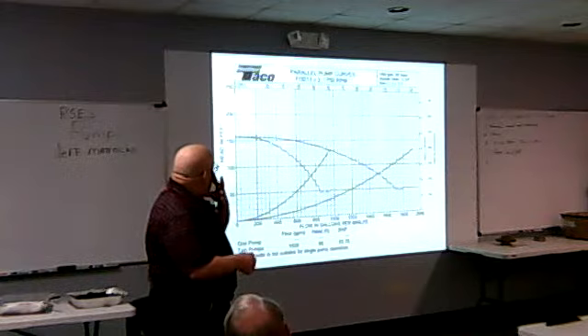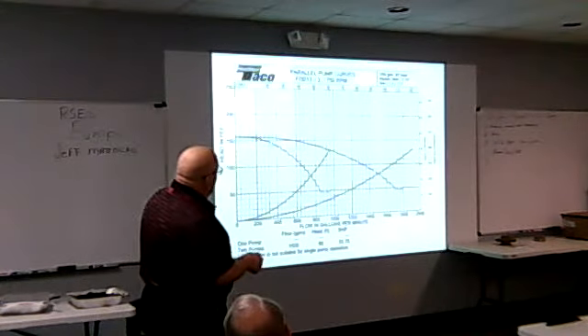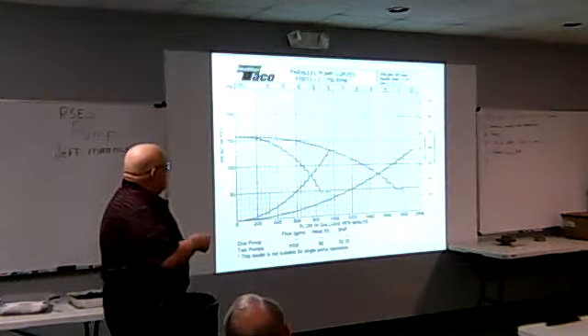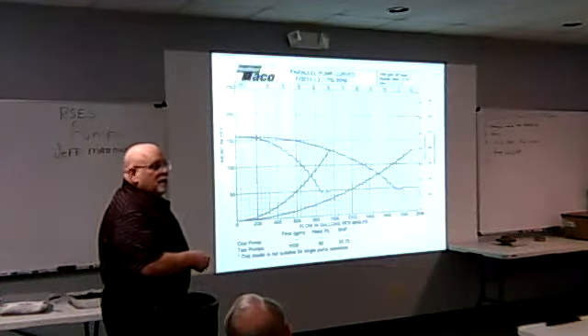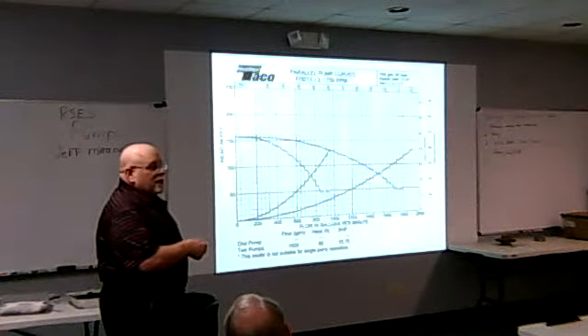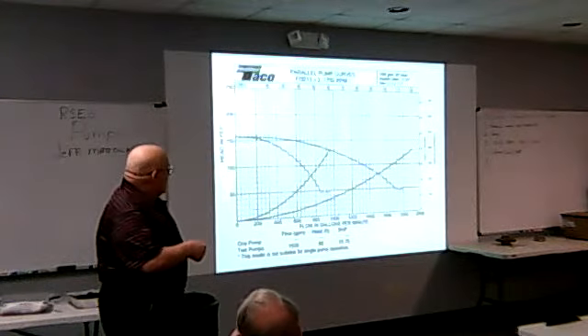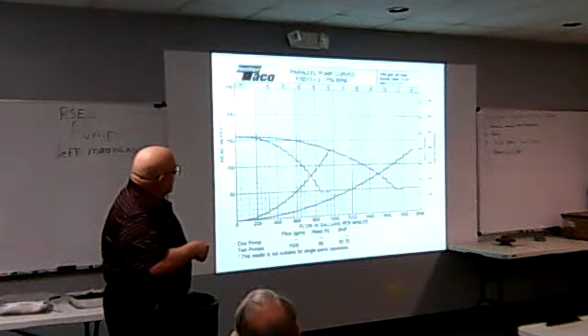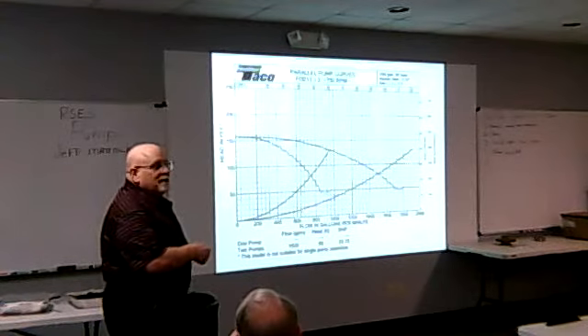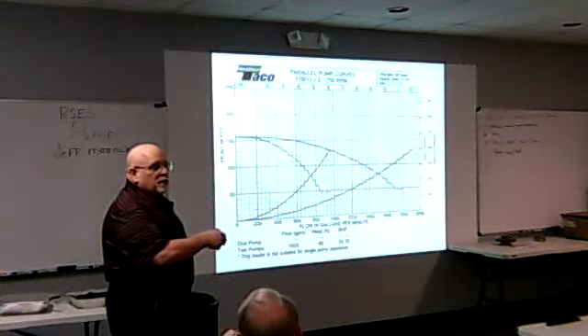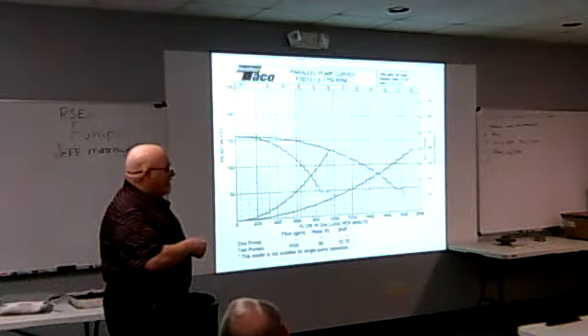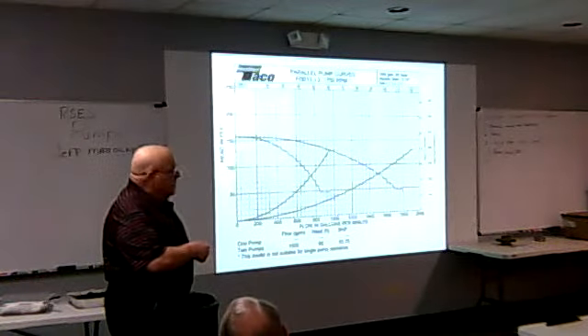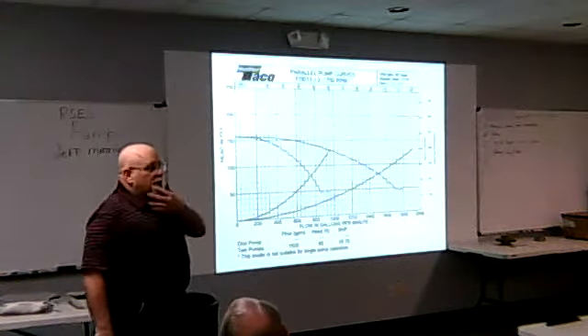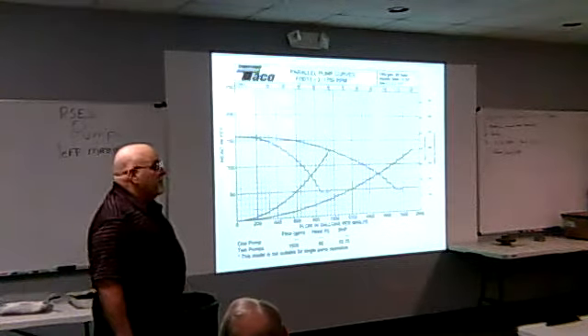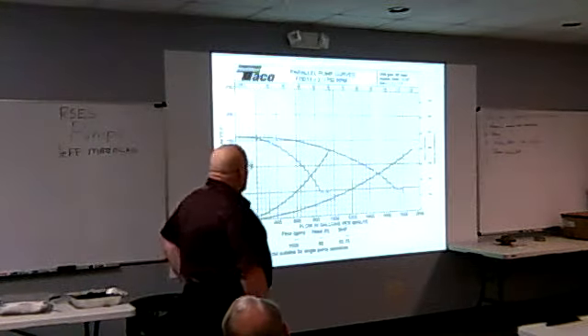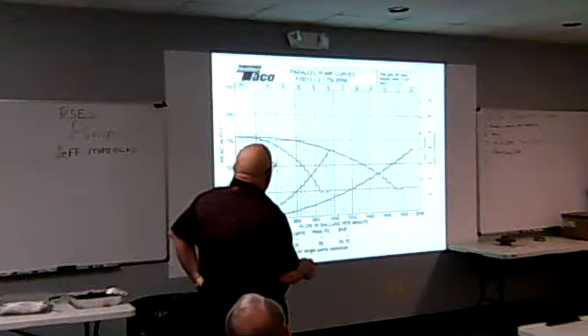You have to be careful when you do this. If your new system curve looks like this and doesn't touch the original pump curve, this pump would kick from parallel. Guess what's going to happen? The single pump is going to try to run on its old system curve here, and it can't get there from here. This is our new system curve with the full flow. This pump is no good for that selection. This has to cross. So it stops where it says P1, P2 on the left. It does not go to the right.